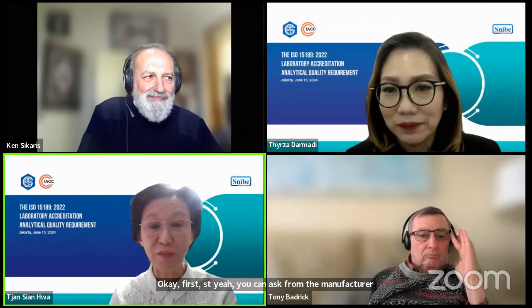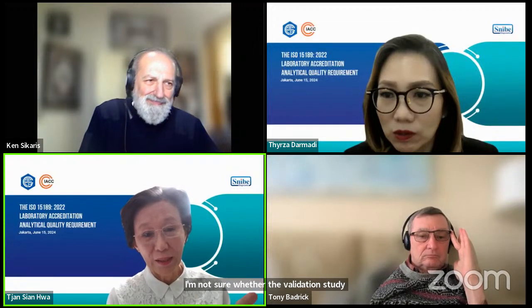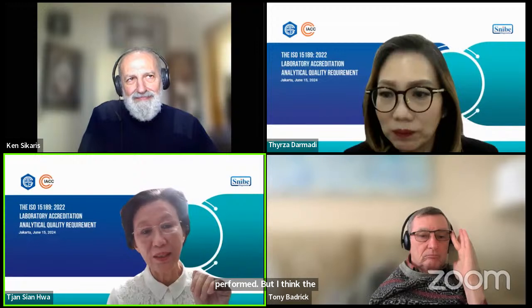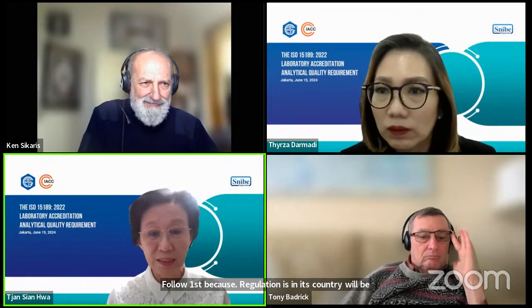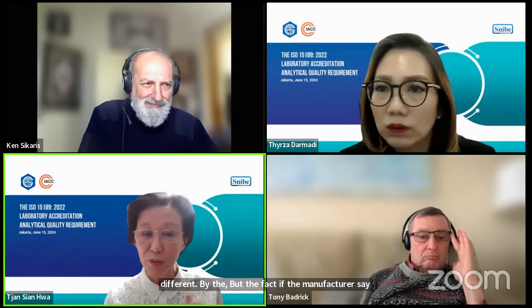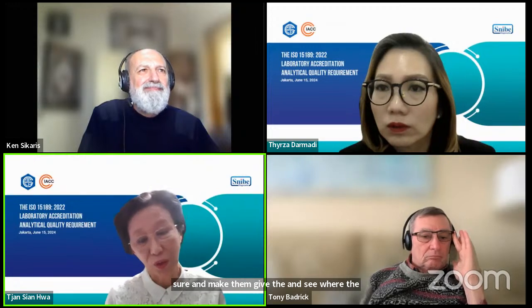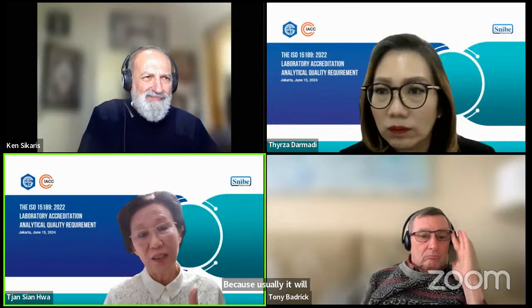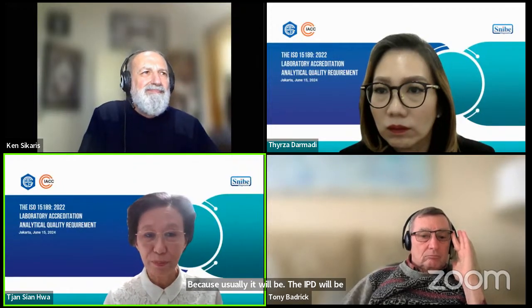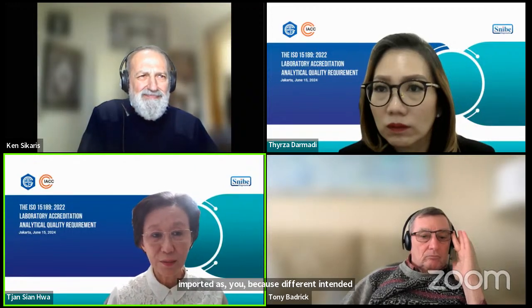Okay. First, you can ask the manufacturer whether they have already done the validation study. If you are not sure whether the validation study has been performed, I think the local regulation should be followed first, because the regulation in each country will be different, whether this is an RUO or not. But if the manufacturer says that this is already validated, maybe you have to make sure they give you the validation study and see whether it is appropriate or not. Usually it will be regulated as an IVD also, but maybe something else makes it imported as RUO, maybe because of a different intended use or something. This must be clear first.